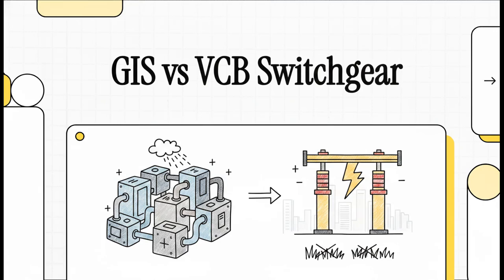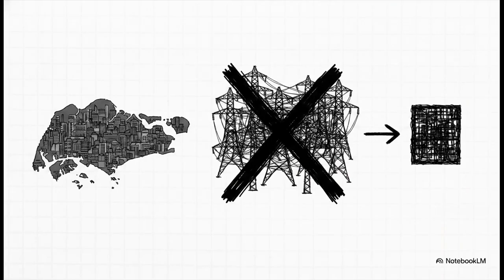Today, we're jumping right into episode 4.1, Switchgear Configuration and Technology Selection, specifically focusing on GIS versus vacuum breakers. Let's get to it. So, picture this. You're an engineer tasked with building a high-voltage substation in Singapore. It's an incredibly land-scarce, densely populated island, right? You literally do not have the luxury of sprawling open-air fields. Every single square meter comes with a staggering price tag. Singapore's land is just way too expensive for massive old-school switchyards, but electricity demands are absolutely skyrocketing. So what do you do? Well, engineers had to make a very deliberate tier-by-tier technology choice to drastically shrink these substation footprints right from the ground up.